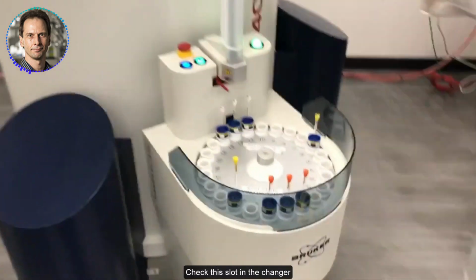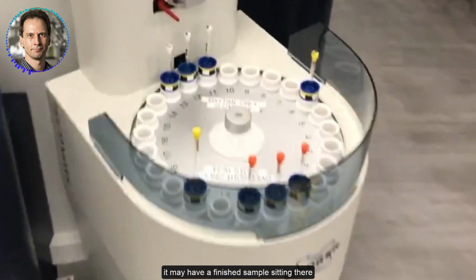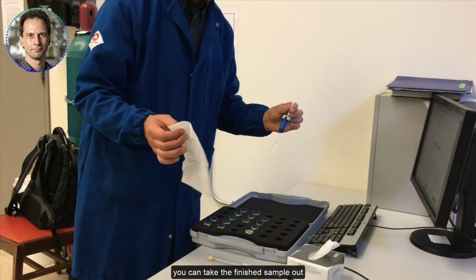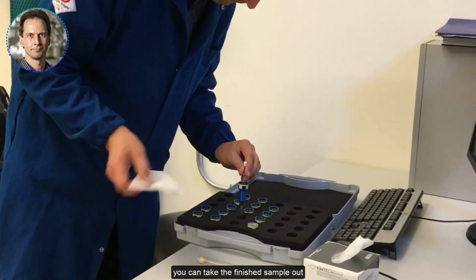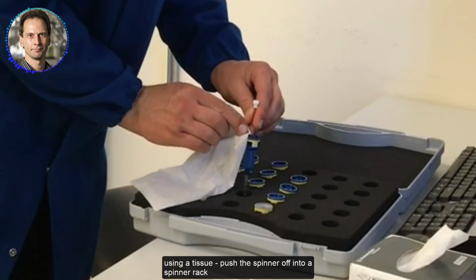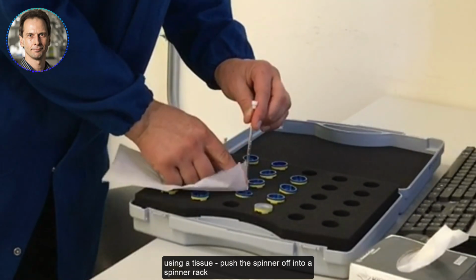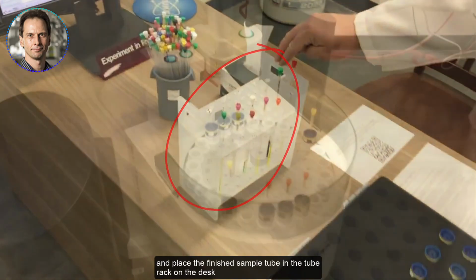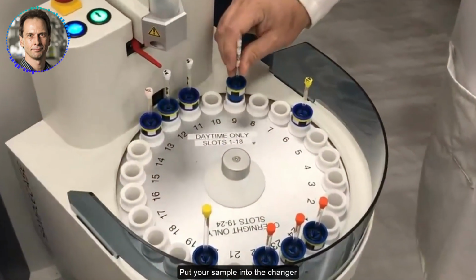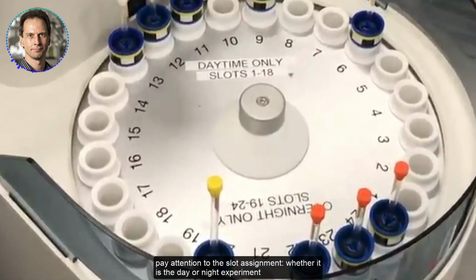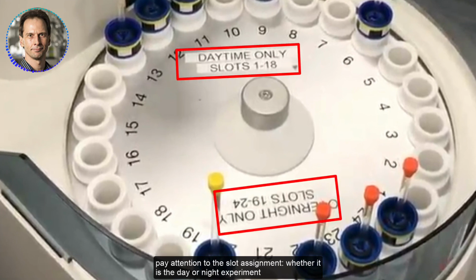Check this slot in the changer. It may have a finished sample sitting there. You can take the finished sample out. Using a tissue, push the spinner off into a spinner rack and place the finished sample tube in the tube rack on the desk. Put your sample into the changer. Pay attention to the slot assignment, whether it is the day or night experiment.